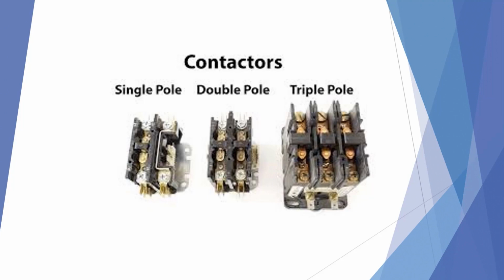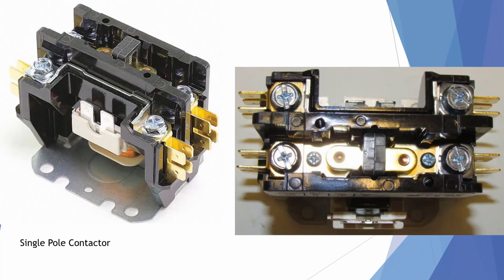Contactors are on and off switches used mainly to turn motors or compressors on and off. They come in a variety of sizes and configurations for all voltages and amp draws. The single pole contactor is the most common contactor seen in a lot of residential air conditioners. Often the single pole that remains closed all the time is used to energize crankcase heat to the compressor in the off cycle.